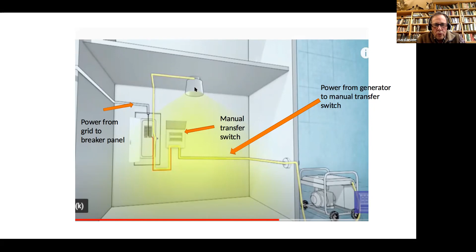Things get rewired a bit. So the power, instead of going to a breaker in this panel, bypasses that panel and comes over to a manual transfer switch. Under normal conditions, with grid power, the switch is left in one position and power goes back out to the appliance. When you throw the switch, you disconnect from grid power so you don't hurt the lineman, and you switch to backup power, which comes in through the manual transfer switch and out to wherever your appliances are. It's a pretty elegant and fairly simple way to do this, just at the throw of a switch.